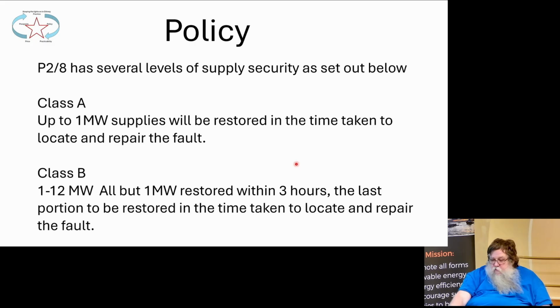Class A, up to 1 megawatt. That means there's no backup at all. It's down to repair time. Class B, 1 to 12 megawatts. All but 1 megawatt must be restored within 3 hours. So if you think about it, you look at the Orkney, it's got a demand of over 30 megawatts. It doesn't count for Class B, it's too big. But if you look at a smaller area, like Stromness, it's going to fall into that 1 to 12 megawatts.